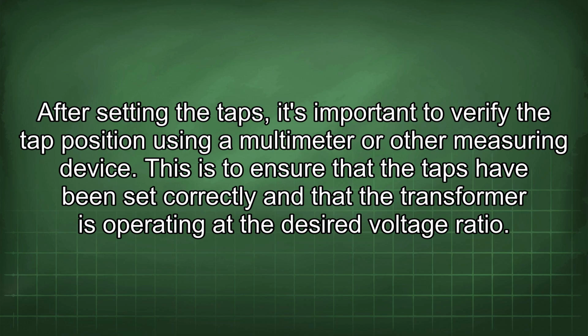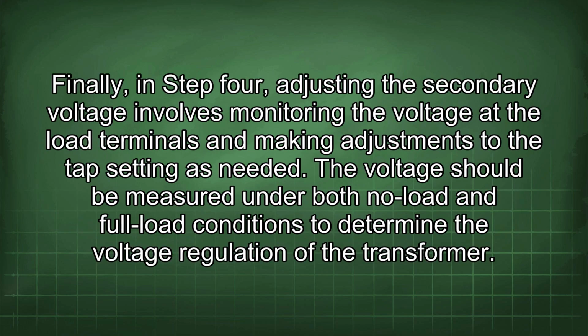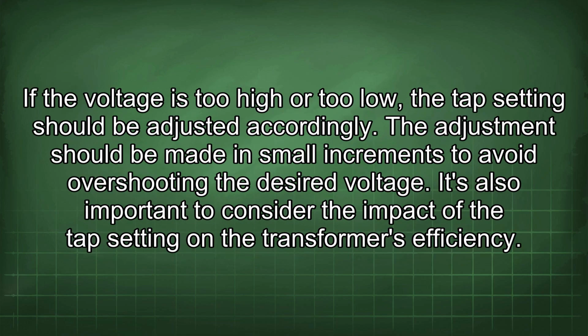Finally, in step 4, adjusting the secondary voltage involves monitoring the voltage at the load terminals and making adjustments to the tap setting as needed. The voltage should be measured under both no load and full load conditions to determine the voltage regulation of the transformer. If the voltage is too high or too low, the tap setting should be adjusted accordingly. The adjustment should be made in small increments to avoid overshooting the desired voltage.